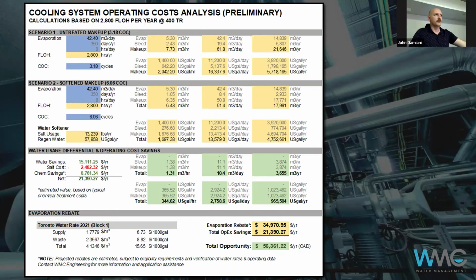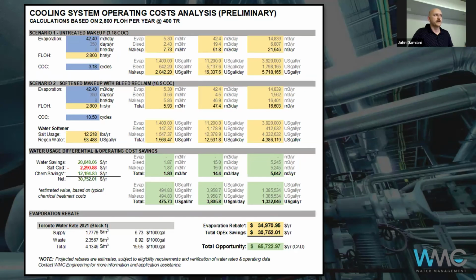This is the second scenario on the same system, where we compare raw makeup untreated with bleed reclaim, which does have higher performance over 10 cycles in this case. But the way cycles work is you get diminishing returns as you go, so once you get past 4, 5, 6 cycles towards 10, you're still getting benefits, but they're diminishing. The total opportunity here was just over 65,000, so about $10,000 more savings per year. That's not nothing.